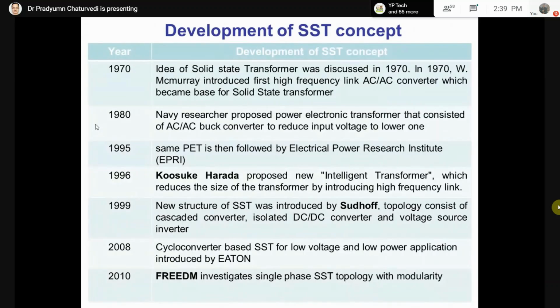The major culprit was the transformer working at 50 hertz. If you are able to operate that at high frequency, then the switches connected across the converters, across the HFT windings, need to switch on and off at very high frequency. At that time only SCR and GTO were available, which could not work at very high frequency. But now, due to development of wide bandgap devices like GaN, this area is accelerating. So there was a huge gap in the different milestones of this research.